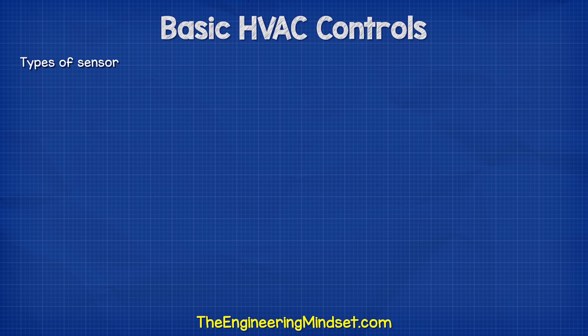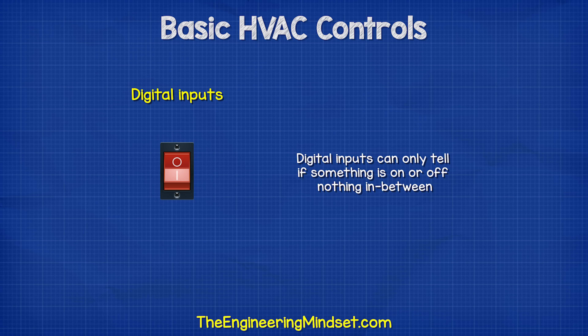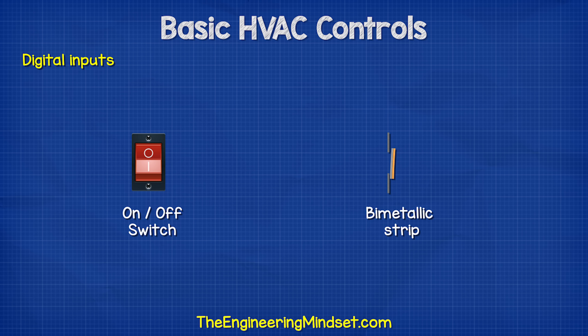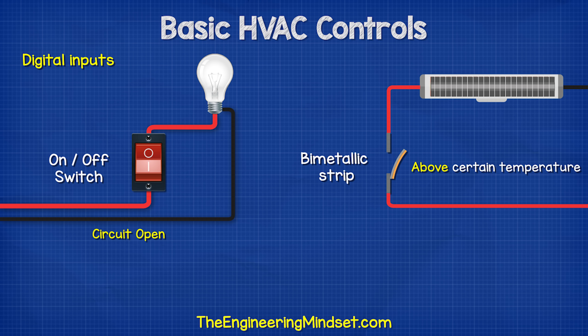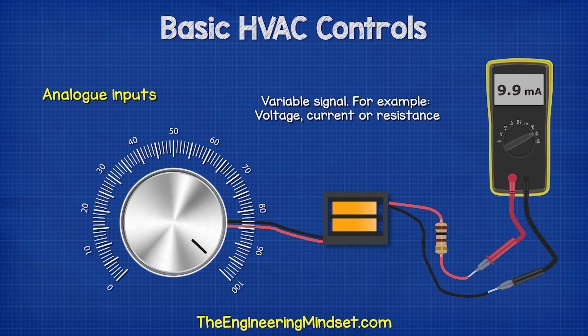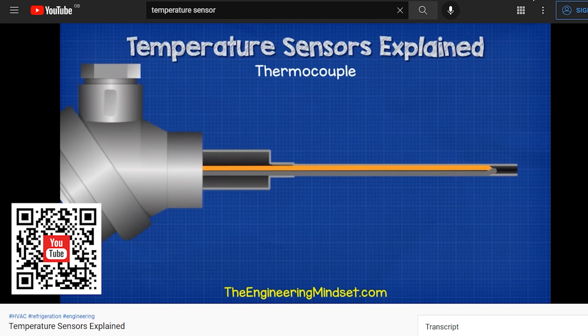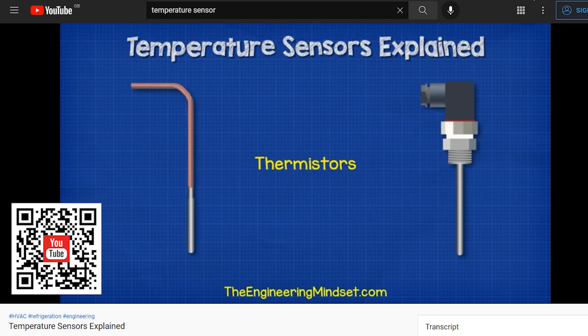We have two main types of sensors: digital and analog. Digital inputs can only tell if something is on or off — nothing in between. For example, an on-off switch or a bimetallic strip. The circuit is either open or closed, so we can only tell if the temperature is above or below a certain value. Analog inputs vary their signal — they might vary in resistance, voltage, or current between a minimum and maximum value. So we can use these to determine the exact temperature or pressure. We have covered how temperature sensors work previously, and I'll leave a link in the video description below.